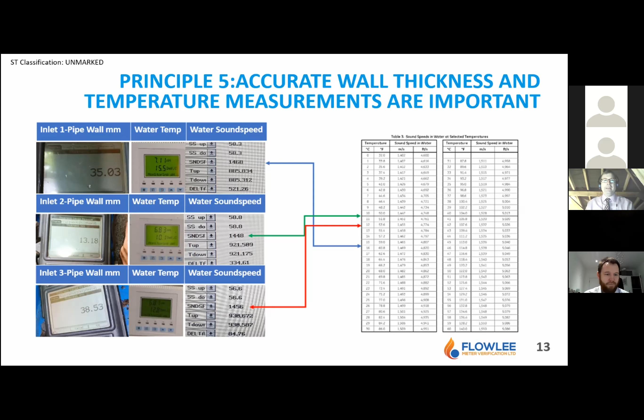We also saw the temperature of the water changed, and we think this is because one of the pipes was getting water from towards the top of the river, and one was abstracting water lower down in the river. So what I'm saying here is, when we put on ultrasonic meters, don't just use default values, or think that the main next to it is exactly like the main that you're about to install on. It's not. We need to do accurate measurements to lower errors.